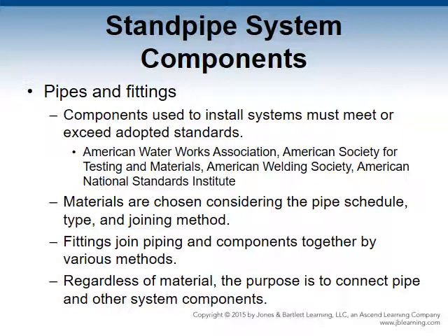Fittings join piping and components together by various methods, such as thread, groove, flange, weld, solder, and brazed. Regardless of material, the purpose is to connect pipe and other system components. All pipe, fittings, and components must be rated for the maximum anticipated system pressure.